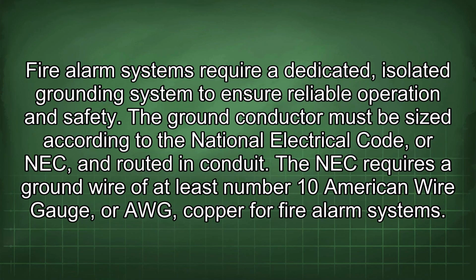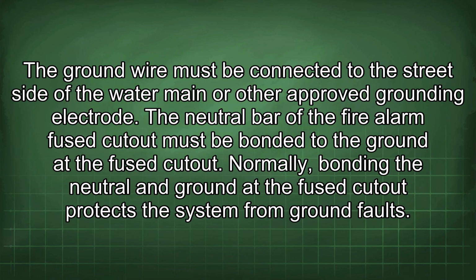Fire alarm systems require a dedicated, isolated grounding system to ensure reliable operation and safety. The ground conductor must be sized according to the National Electrical Code, or NEC, and routed in conduit. The NEC requires a ground wire of at least number 10 American wire gauge, or AWG, copper for fire alarm systems. The ground wire must be connected to the street side of the water main or other approved grounding electrode.